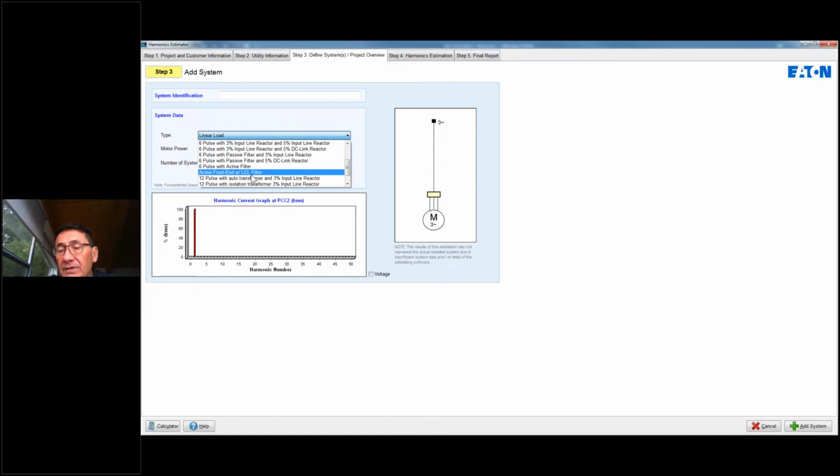That isn't a drive, it's just the front end that points to the line, and then it supplies power out to all the other drives of any brand that you happen to connect to the Mirus output. Mirus is one of 20 companies that I'm aware of that make active front end filters only. They don't make drives. They're in the business of cleaning up the noise that drives create, not through static filters, but through an active filter.